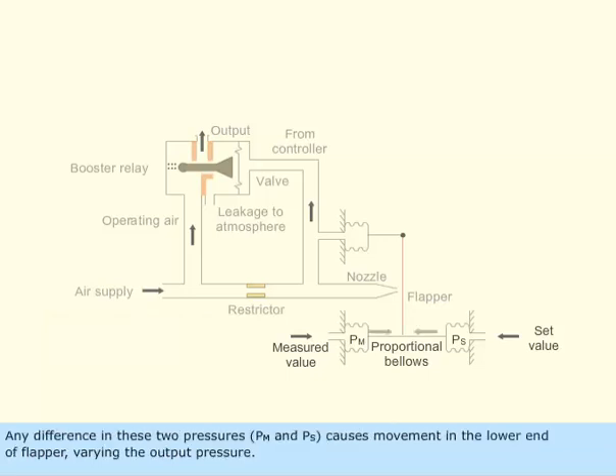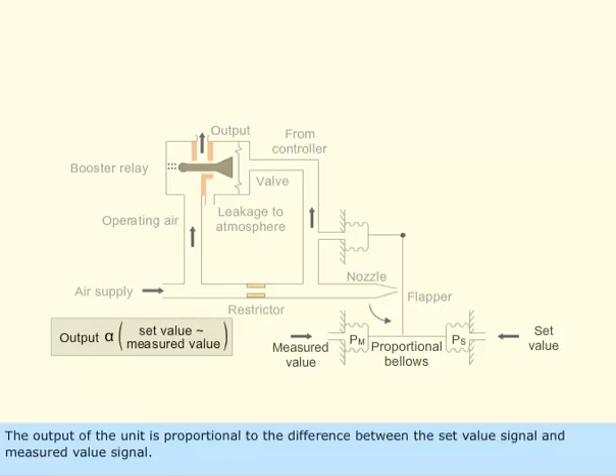Any difference in these two pressures, Pm and Ps, causes movement in the lower end of flapper varying the output pressure. The output of the unit is proportional to the difference between the set value signal and measured value signal.